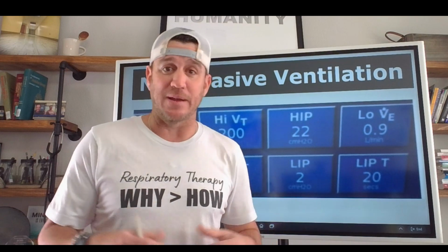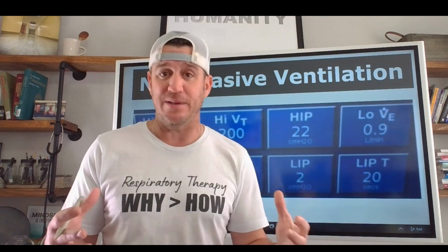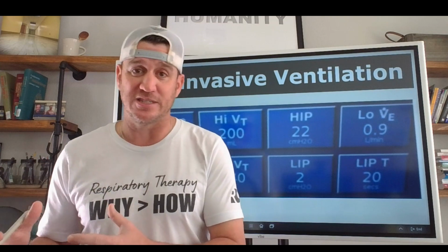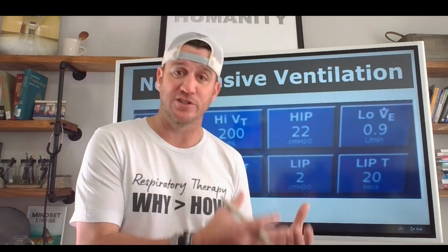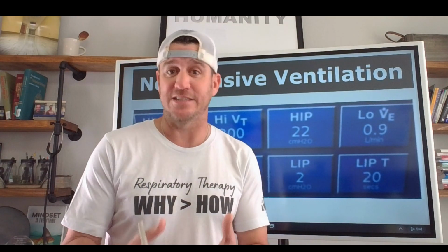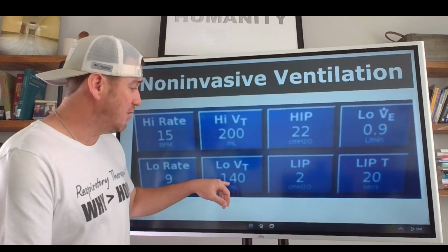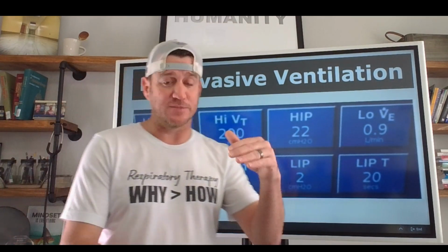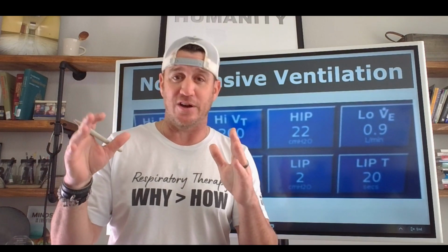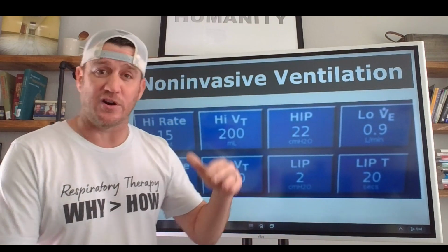Maybe they're getting better. Maybe they're waking up. Maybe whatever it might be. Now the tidal volumes are excessively high. This alarm is going to notify you of that when set appropriately. Same thing with the low tidal volume.